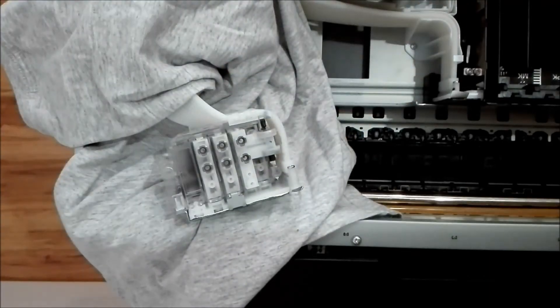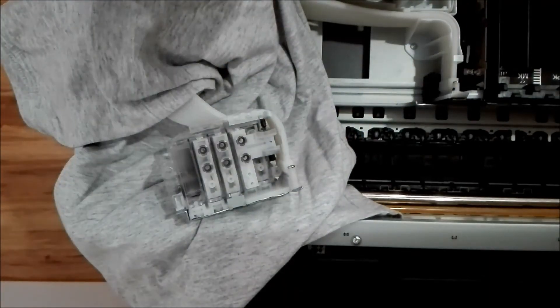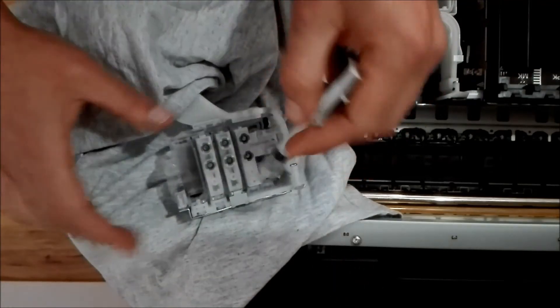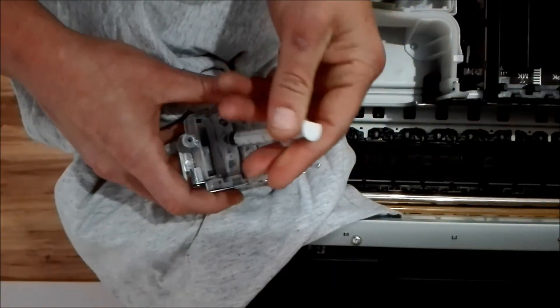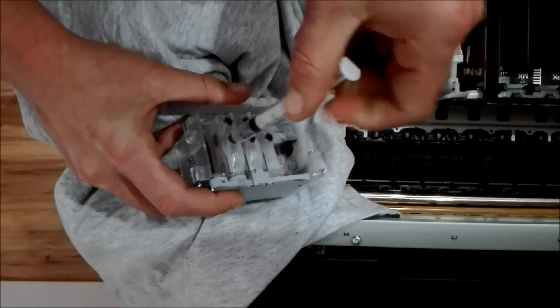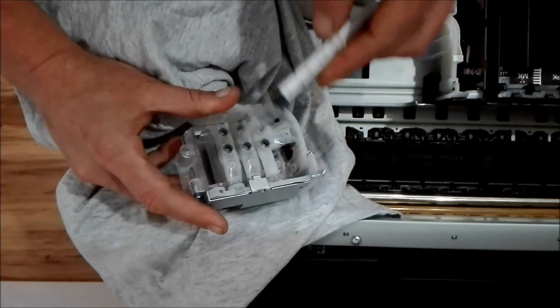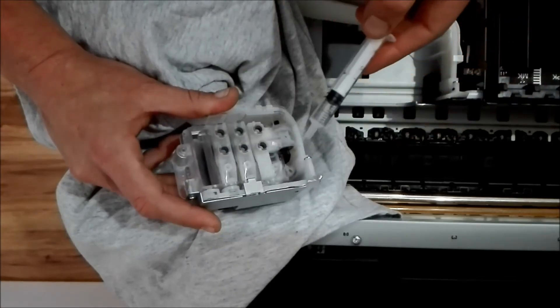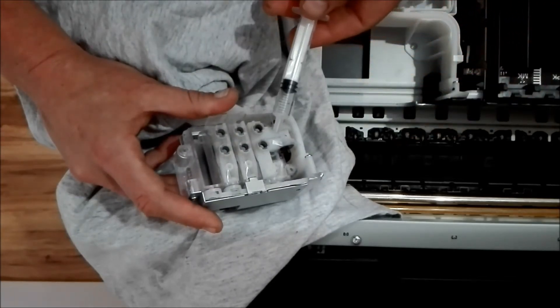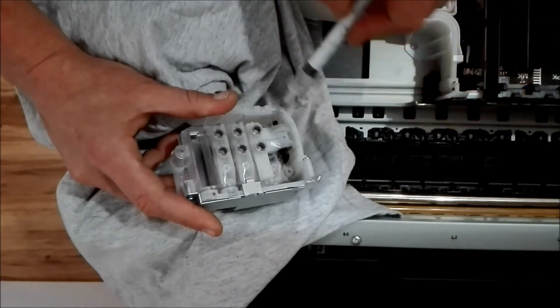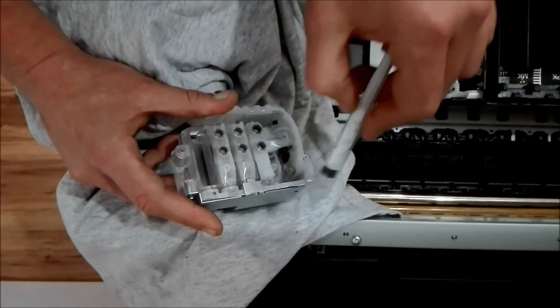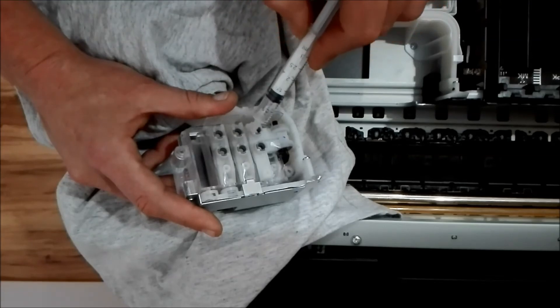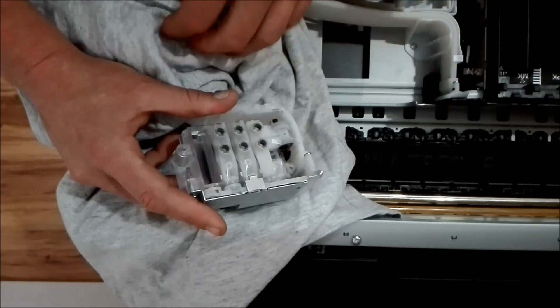And then it's very important, once you've installed the new damper, to take your syringe and just connect it there and pull ink through. This is not only to make sure that the integrity of the damper itself is not compromised, because if the plastic's perforated in any way, you're going to have a problem. But to also make sure that the ink makes it through the selector plates and you don't actually have a blockage there that you need to deal with.